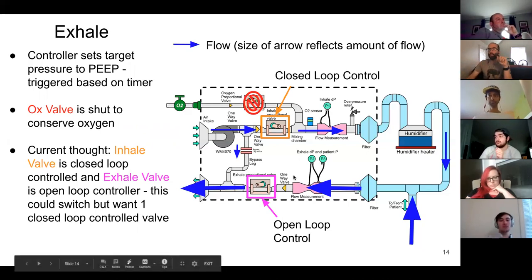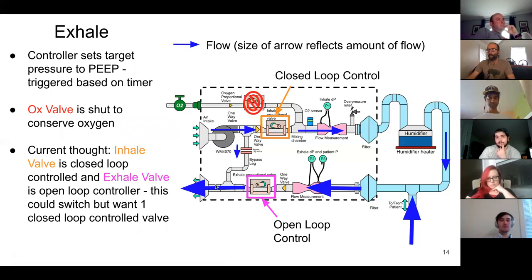Or we could run closed loop control where this is the valve that's controlling patient pressure and closing as the patient exhale ends. Right now, we're going to try and maintain closed loop control just on this one valve to try and simplify the dynamics, but that's definitely up in the air, and we need to play with it. And John, that's something that would be great to get feedback from the system model on. Is that what it's called, model on?